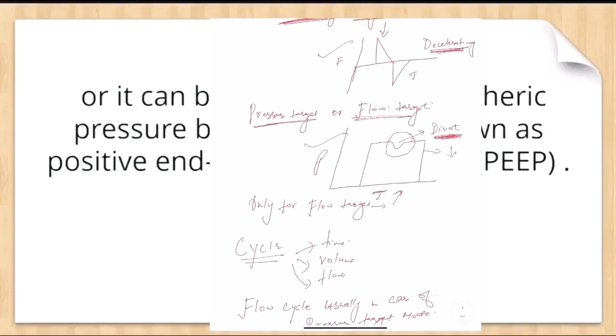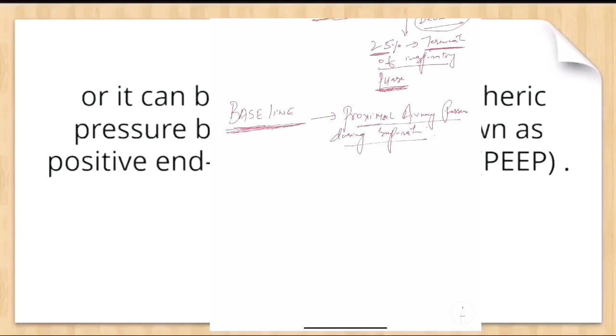Now the other thing is cycle. The cycle could be time cycled, flow cycled, or volume cycled. Now flow is usually cycled in case of the pressure targeted mode. Usually we select 25%, that means if the peak inspiratory flow decreases to 25%, there is termination of the inspiratory phase. Now the last thing, that is the baseline. Baseline is the proximal airway pressure during the expiratory phase.